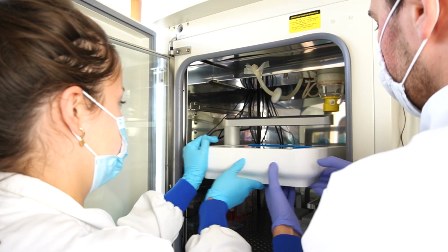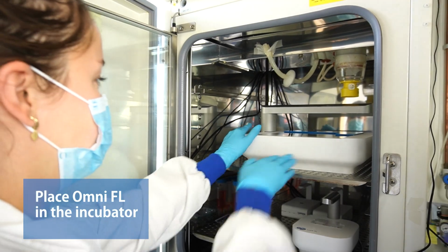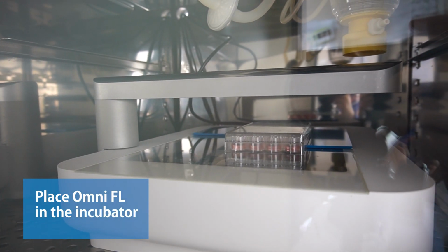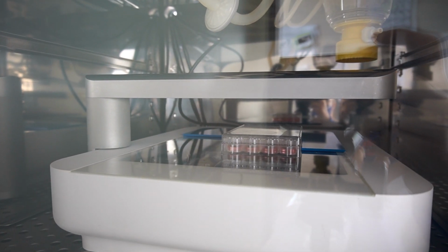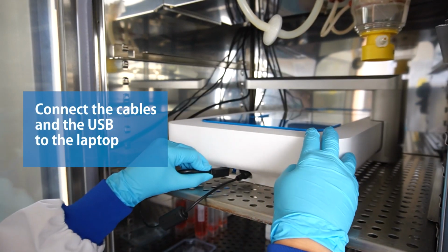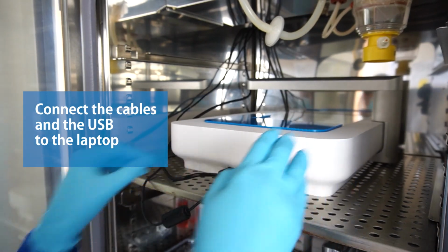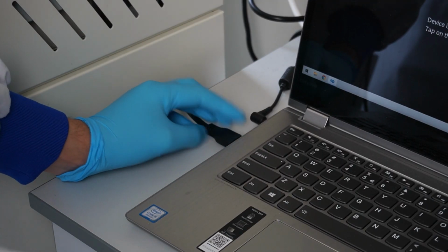To image all your samples in their optimal environment without disturbing your cells, install the OmniFL in your incubator. Make sure the light arc can move freely. Connect the device to the power supply via the adapter and subsequently to the laptop via the USB cable.